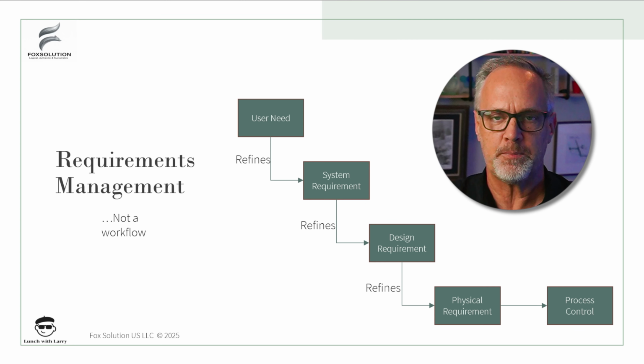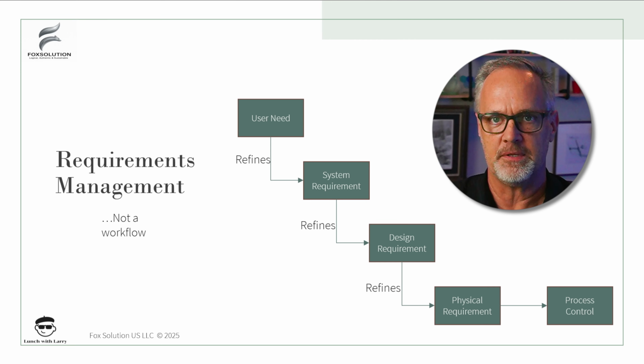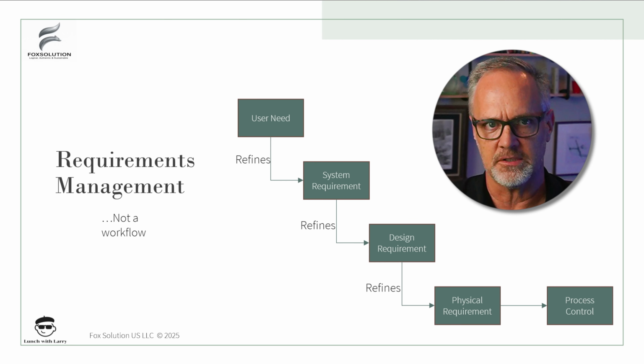These are really aspects of a data decomposition, and it won't be uncommon for us to bring in an internal standard that plugs in some design requirements that don't have system requirements attached to them. And we'll need to run that traceability up to user needs as we develop the design, but it doesn't mean I need to do one before the other or necessarily that I have to have these in place before I start doing any design work. This is more, how do we explain what the inputs to the design are so that eventually when we get completed with the design, we'll be able to explain how the device works and then show that traceability to our evidence. So that's really what this is all about. It's not a workflow, it's really a decomposition, a logical decomposition model.